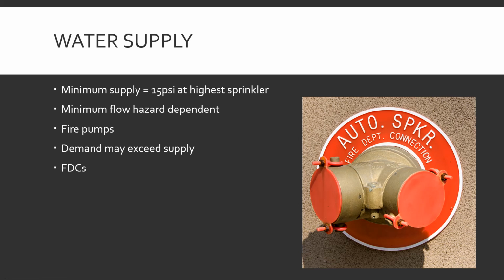Fire pumps. They assist the system when a certain low pressure is met. As I said before, usually sprinkler systems are connected to the municipal water system in a city. So they're getting 60 psi or whatever it is coming in off the street. When there's a big fire and they're flowing a lot, sprinkler heads are open, pressure will go down. So backup fire pumps will go, all right, now I've dropped to 20 psi, I've got to kick on and help boost that pressure up to where it should be so everything works correctly.